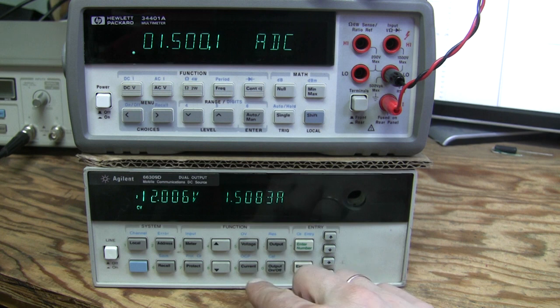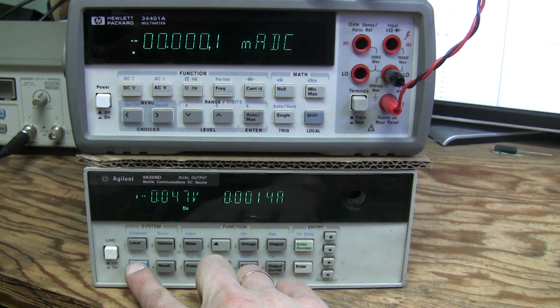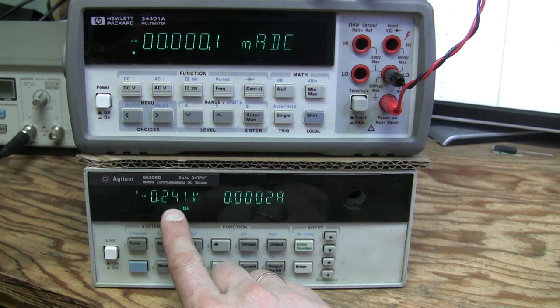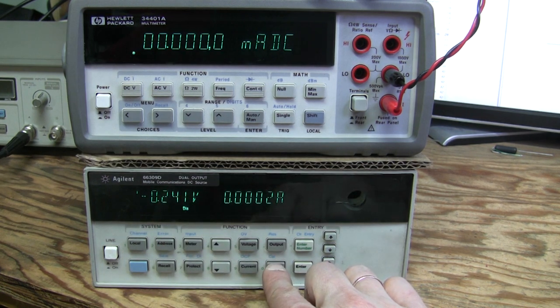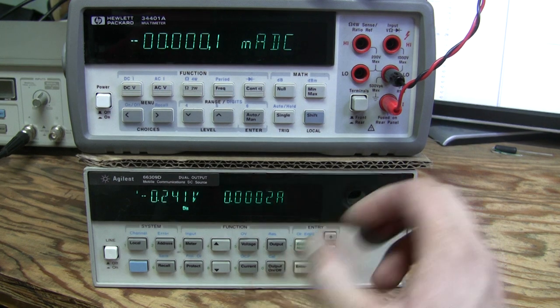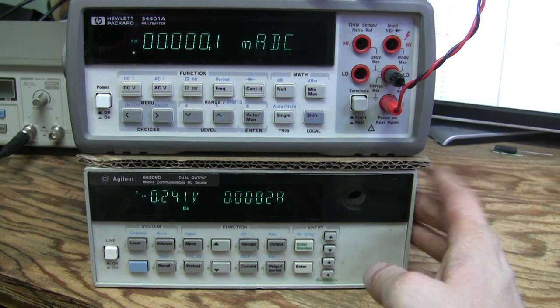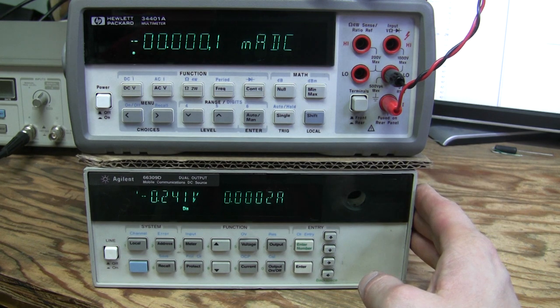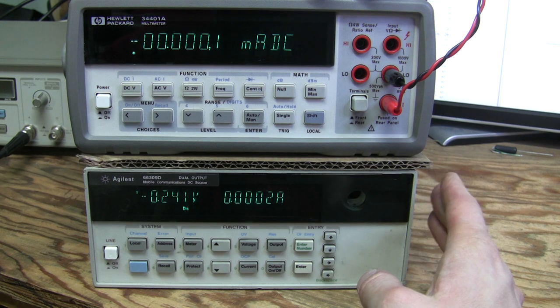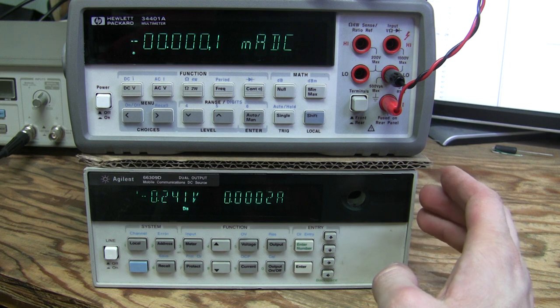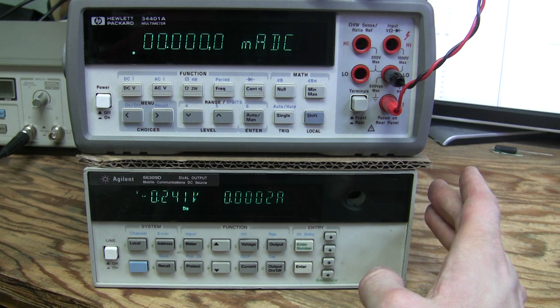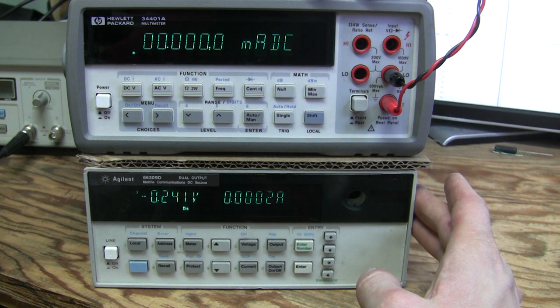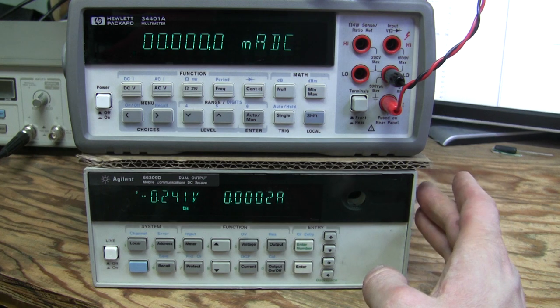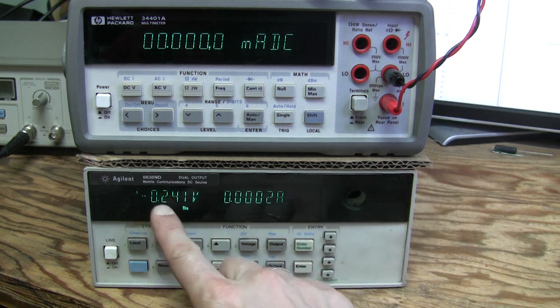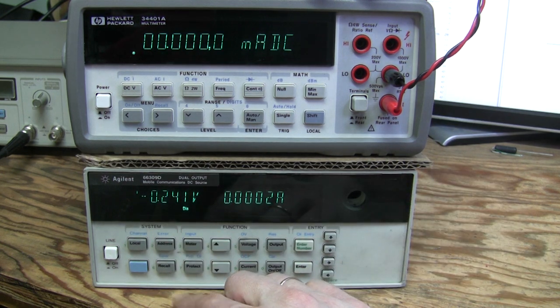And by the way, regarding this problem of offset on the voltage when the output is off, I read the manual, and because this unit has the solid state relays option, the manual says that in this case, with output disabled, the output voltage readback will not be correct. This is because the sense relay is open, effectively breaking the readback path. The voltage readback will be a small negative number. Well, I'm not sure if this qualifies as a small negative number.